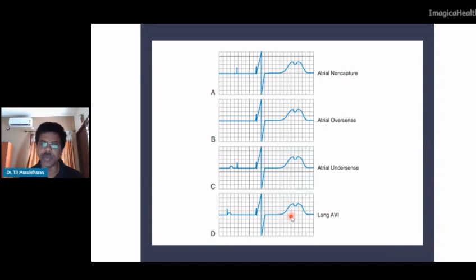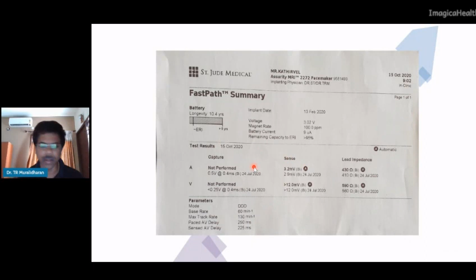In this patient, our patient, we had set not only a long AV delay, we kept the PVARP shorter to help the patient. So coming back to the patient's pacemaker parameters, the dual chamber pacemaker, his paced AV delay was kept at 250 and sensed AV delay at 225. We thought, since he had intermittent complete heart block, we didn't want to worsen his LV function further by pacing-induced cardiomyopathy. We thought we were helping him by keeping the AV delay longer, allowing for the intrinsic beat to go on and the pacemaker to come only when necessary. But that became counterproductive in him by setting a milieu for a pacemaker-mediated tachycardia.